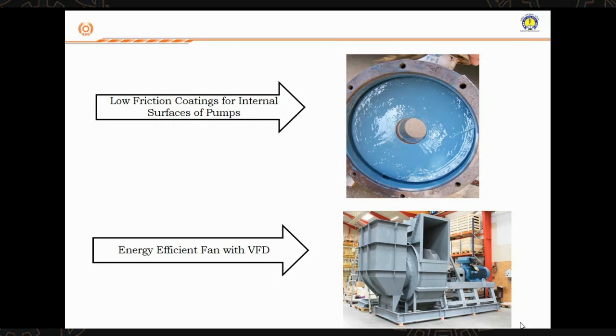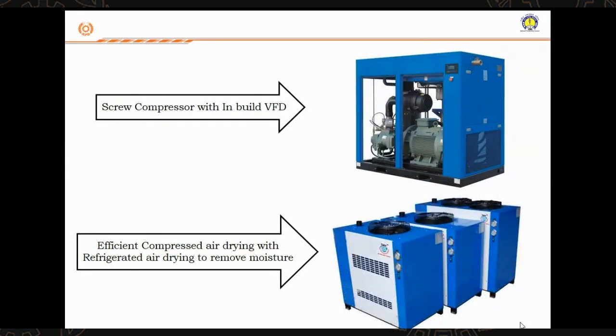Now all the new fans, very high efficient premium fans, are available with higher efficiencies, and they also have an inbuilt VFD arrangement. Take the chiller: where you have SME bulk drug manufacturing, or where you have a chilled water requirement for your process or for cooling of your building, you have nowadays screw compressors available with inbuilt VFDs. So the kilowatt hour per ton has been drastically reduced when compared to reciprocating compressors. But still, whether you need to use a reciprocating compressor, screw compressor, or a centrifugal compressor, it all depends upon the requirement and the volumes of water required.